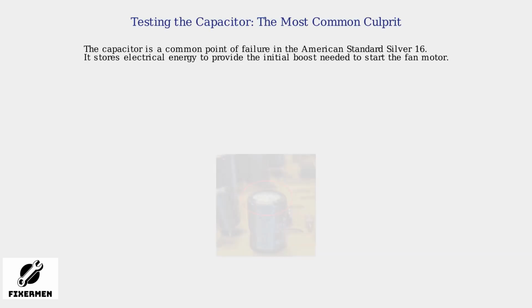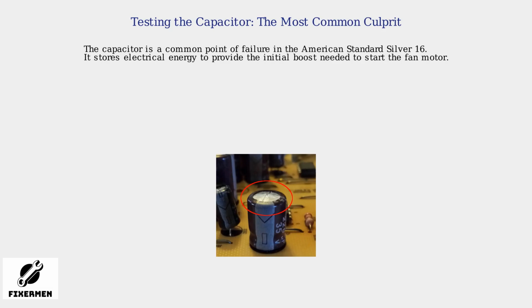Finally, test if the fan blades can spin freely by gently turning them by hand. If the blades are difficult to turn, there may be a mechanical issue requiring further attention. If the blades are hard to turn manually, this could indicate a mechanical problem with the fan motor or bearings. The capacitor is a common point of failure in the American Standard Silver 16 outdoor fan system. It acts as a small battery, storing electrical energy to provide the initial boost needed to start the fan motor.